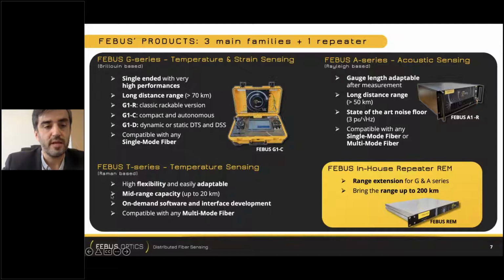Third family I will present today, it's Raman-based DTS, so distributed temperature sensing system. It is highly flexible, it's very cost effective. It has a mid-range capacity of 20 kilometers. It is operating on multimode fiber only, and this is the temperature sensing system clearly well suited for well applications. So that's why we're gonna see a lot of measurements coming from this instrument.